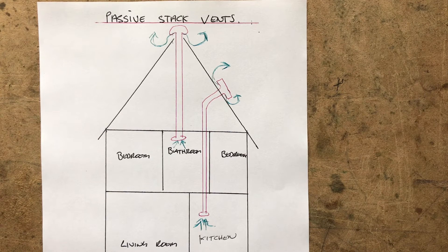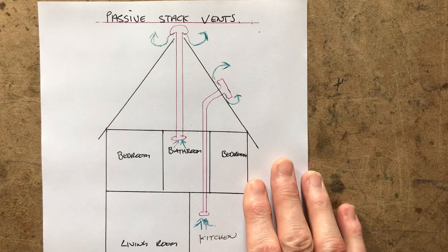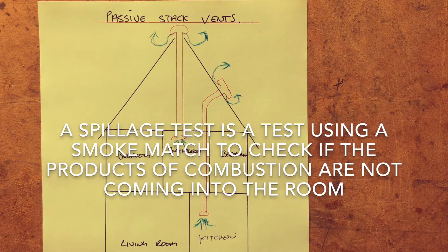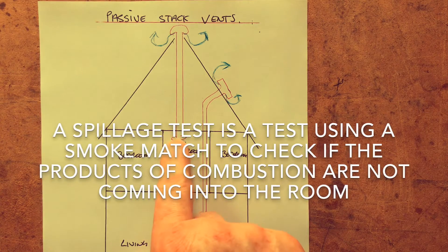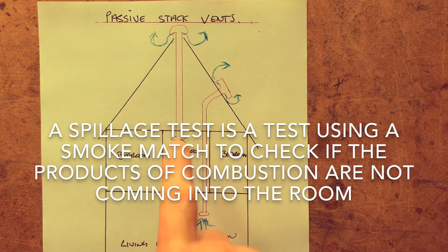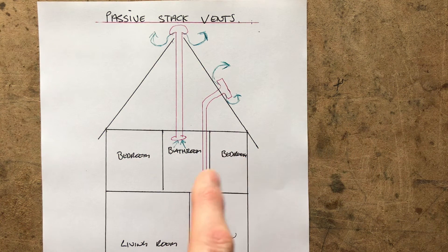For the purpose of calculating ventilation for a gas appliance, any passive stack ventilation systems should be ignored and not considered — this is what many engineers don't realise. We look at the appliance independently and calculate ventilation from the manufacturer's instructions and regulations. Where passive stacks do come in is when we're carrying out a spillage test on an open-flued appliance: we must always make sure these vents are open first, do the spillage test, then close the vents and test again.